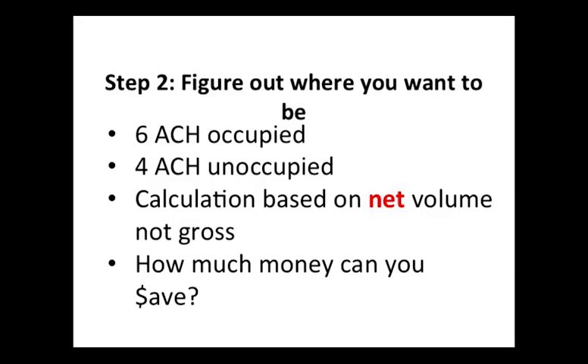So we did a little bit more, and we said, is the air changes per hour based on straight geometric progression, or can we do a calculated value? In other words, take advantage of the fact that there's equipment, ductwork, and so forth. Turns out we hired SMD, Steve DiGiacomo, and he said on average your lab spaces are about 1/3 taken up by other stuff. So when we did our tabulation for doing the rebalance, we based it on the lower air volumes, or volume of the space, and so forth.